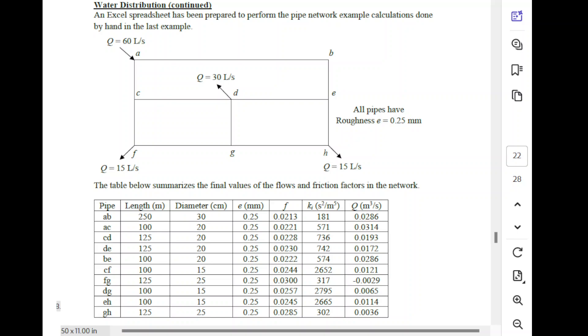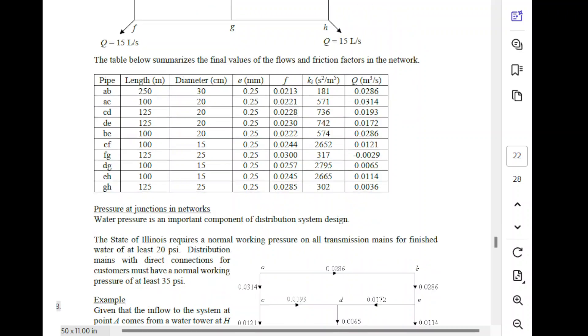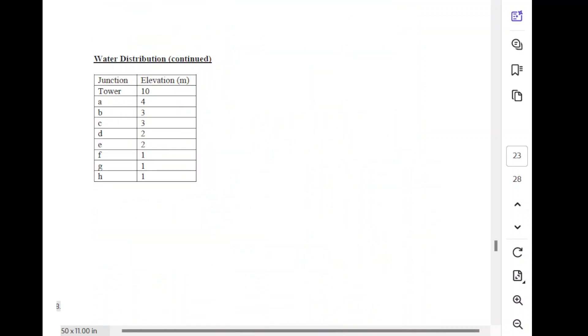All the pipes have a roughness height of 0.25 millimeters, and the other data for the pipes — lengths, diameters, and roughness height — are all given in the table here. The elevation at each of the nodes is also needed to get the pressure everywhere, and those values are provided in this table. I'm going to be working with those values to input into EPANET, and then we'll see if we can get the same answer that I got in Excel.